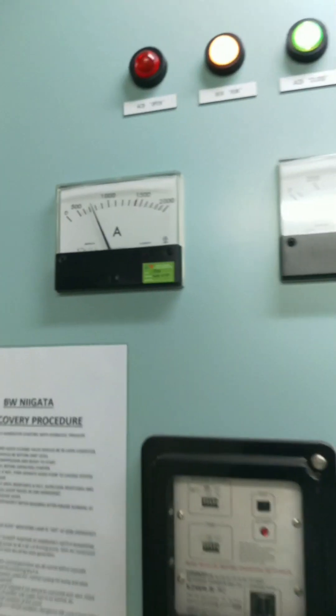Let me start the DO pump for topping up the diesel oil service tank. As you can see, number two generator is on load, number one generator is on first standby, and number three generator is on second standby. Check the load, frequency, and amps of all the pumps, and check whether all the standby pumps are in auto — if not, please confirm with the previous watch keeper.